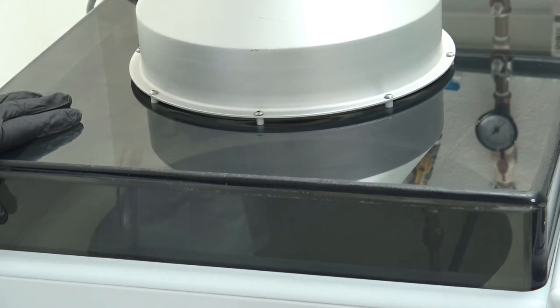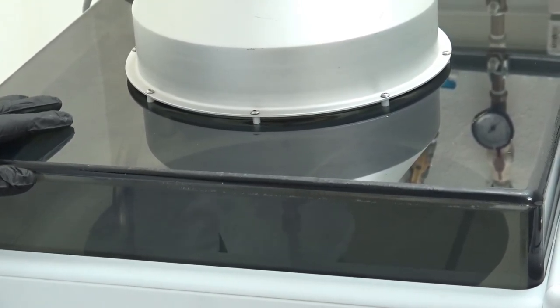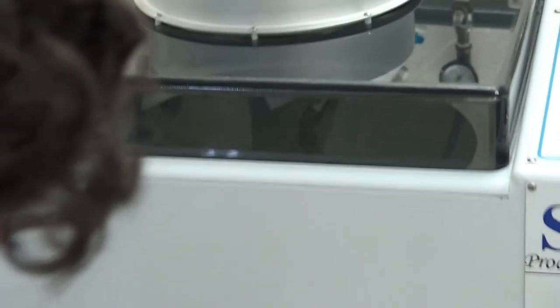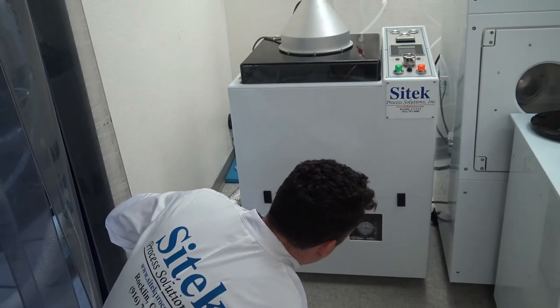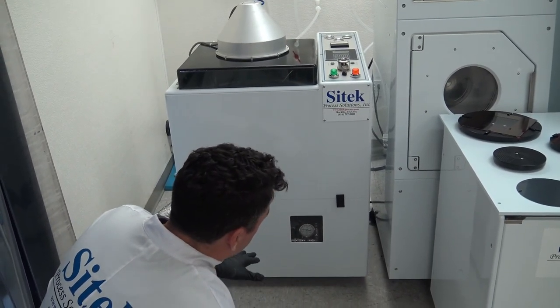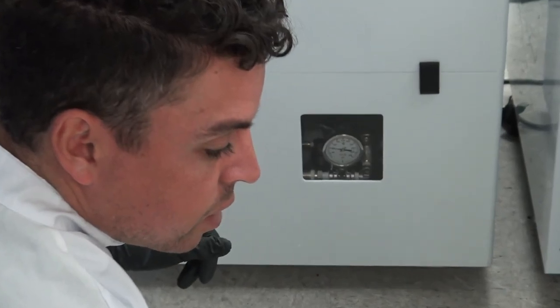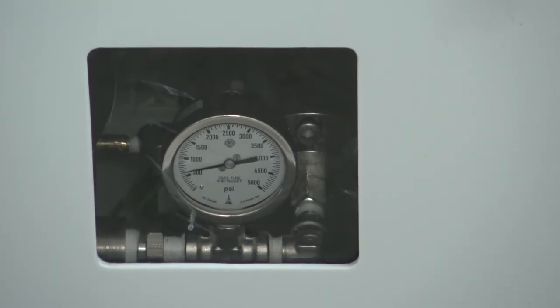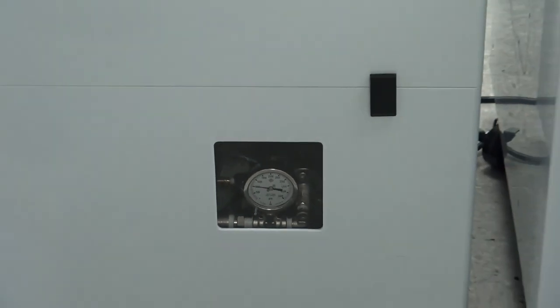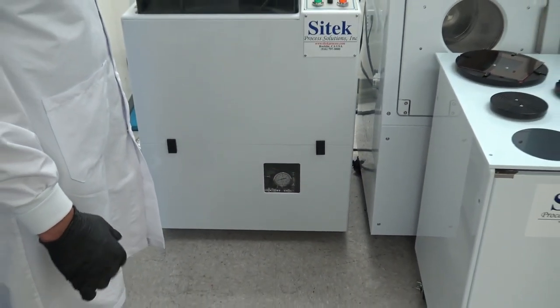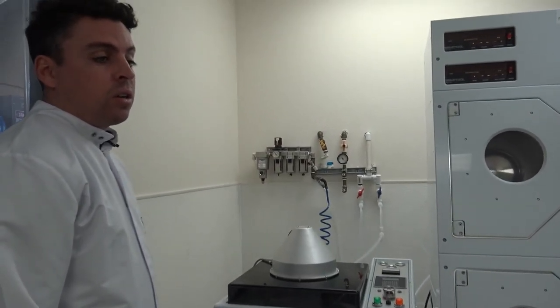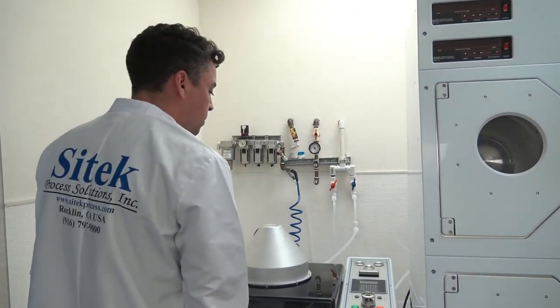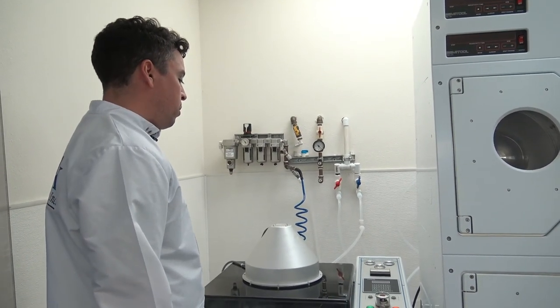We are now moving into the high-pressure, and I can see the arm moving back and forth across the surface. I'm taking a look down here, and our pump is currently pumping at about 1,000 PSI. I'll actually adjust this afterwards to get up to about 1,500 PSI. That's more typical for substrate cleaning pressure. One aspect you have to watch out for is if the pressure is too high, it can damage the masks, or it can break substrates. However, that's a pretty high pressure. You're looking at more 2,000, 2,500 PSI is when you have more risk for that issue to happen. So we have three more seconds of the high pressure.